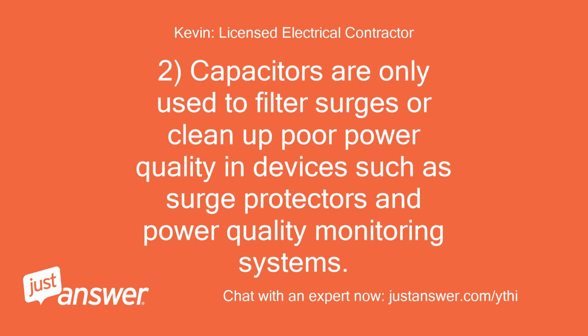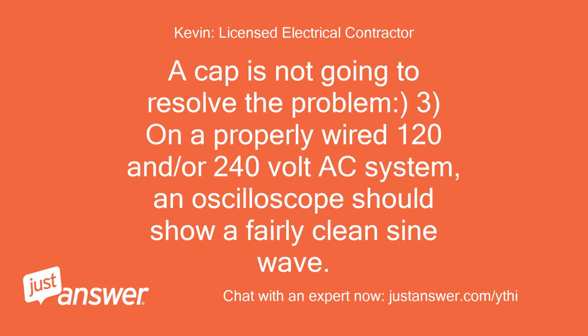2. Capacitors are only used to filter surges or clean up poor power quality in devices such as surge protectors and power quality monitoring systems. A cap is not going to resolve the problem. 3. On a properly wired 120 and or 240 volt AC system, an oscilloscope should show a fairly clean sine wave.